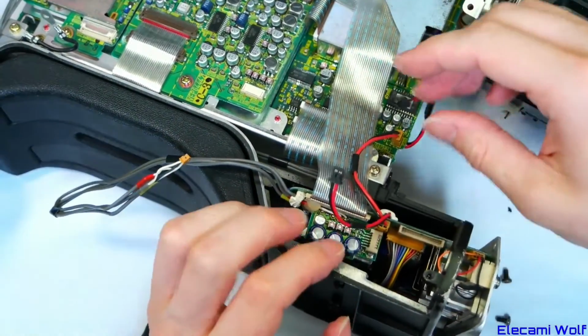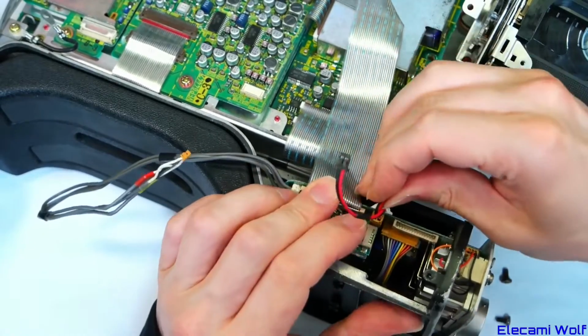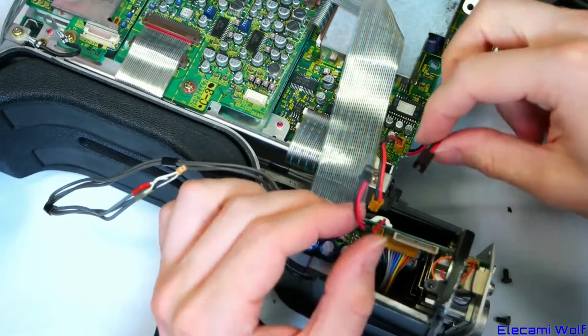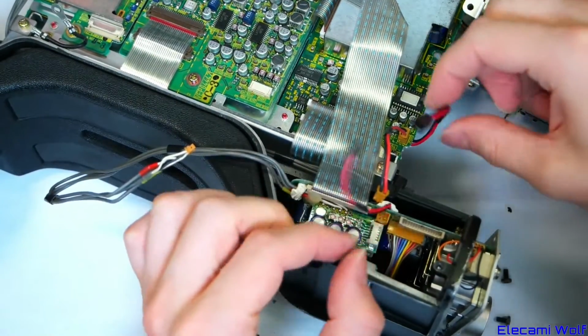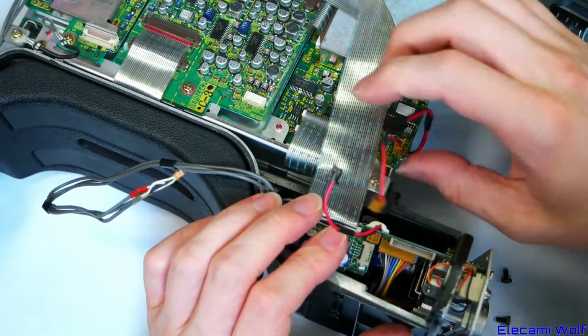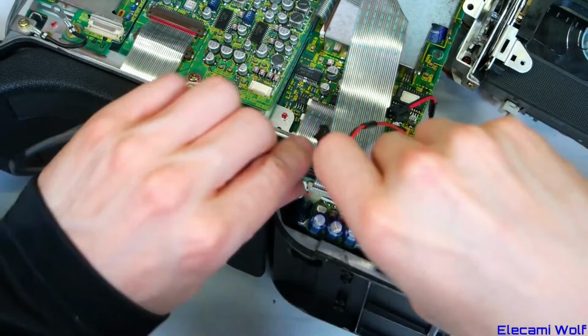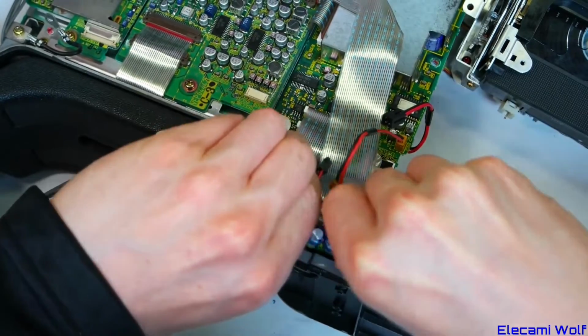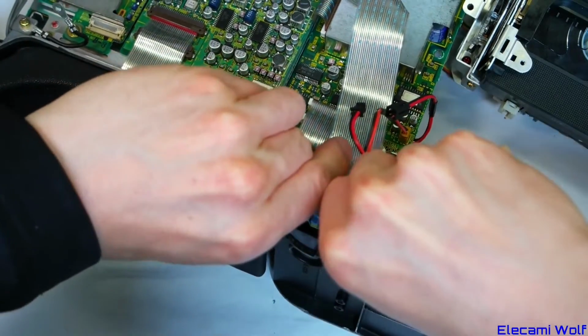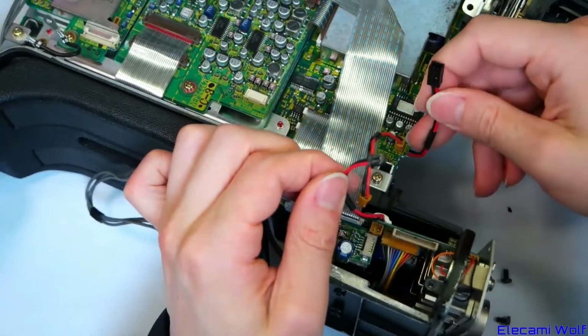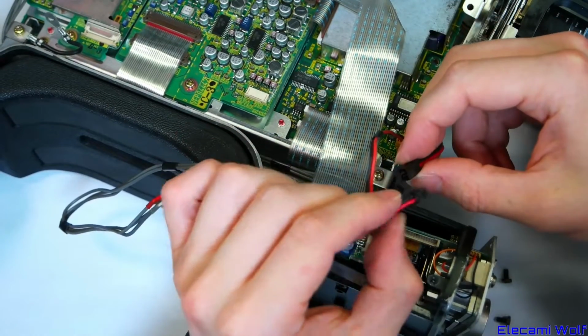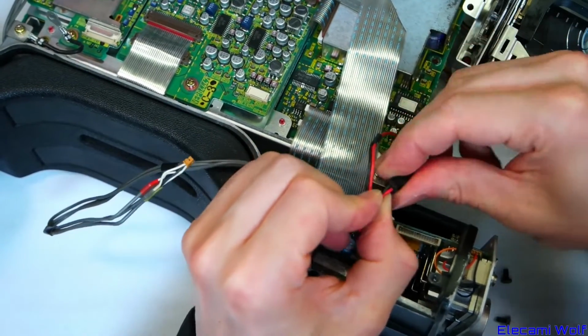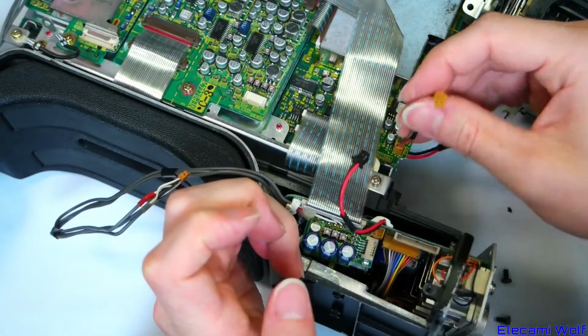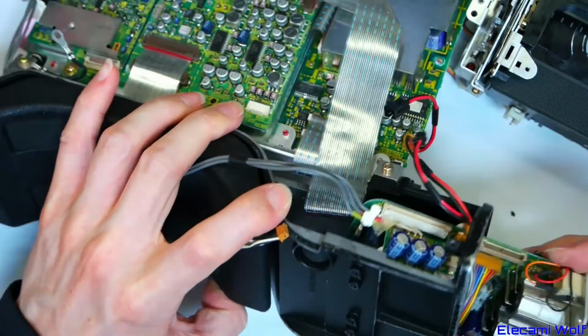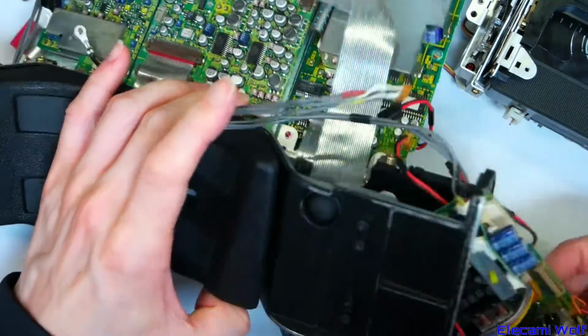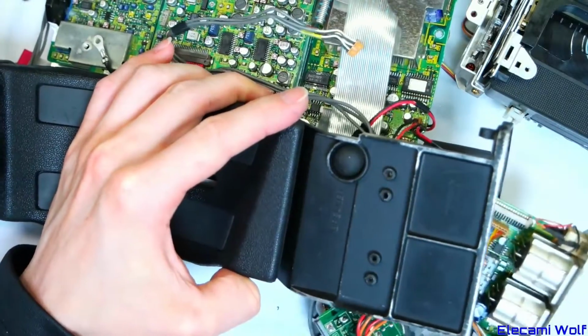Huh. So they must have found that these wires are too thin, and they've done a bodge with this, which is in parallel. That's interesting. There must have been too much voltage drop. So there's a factory fitted update of a little cable assembly with an inline connector in parallel with that. Nope. That's all that can feed through.